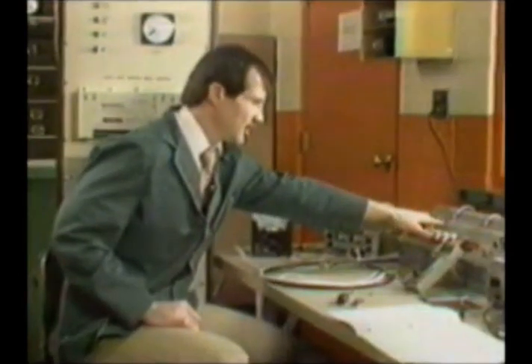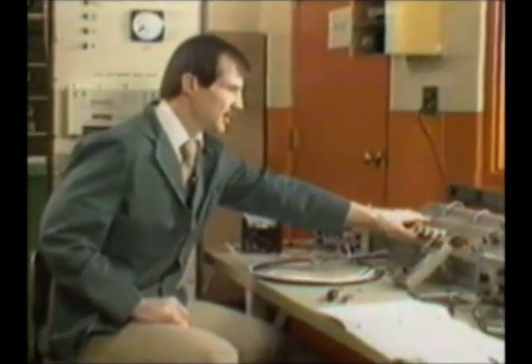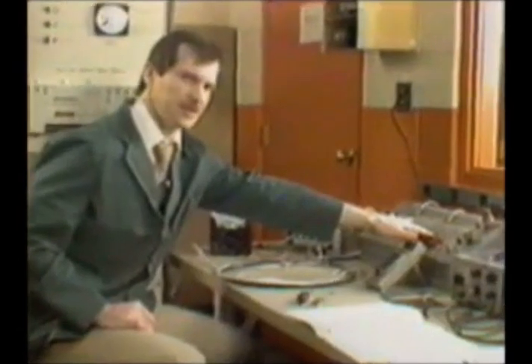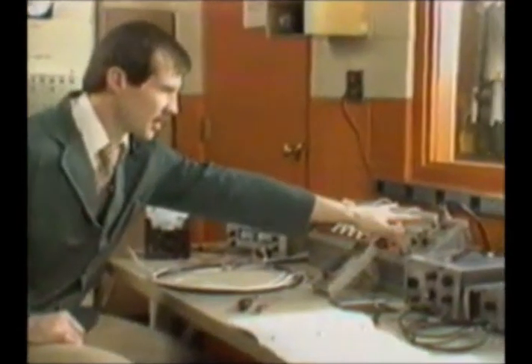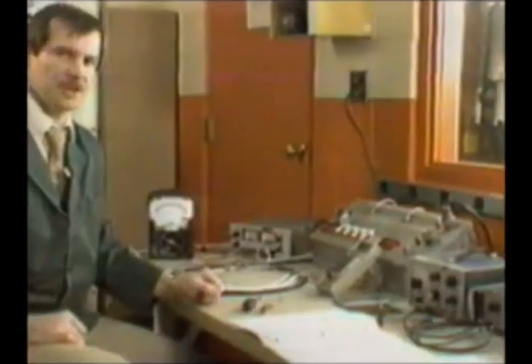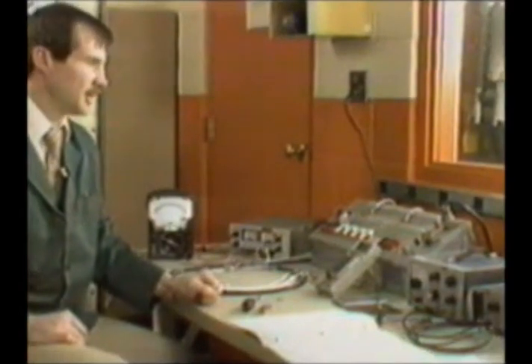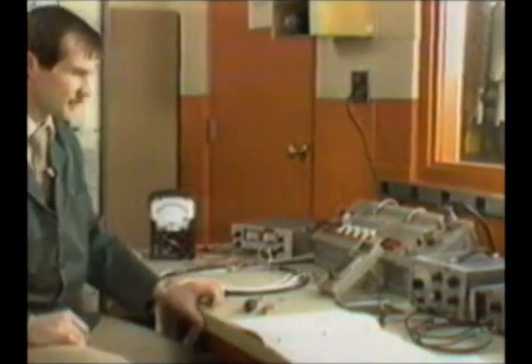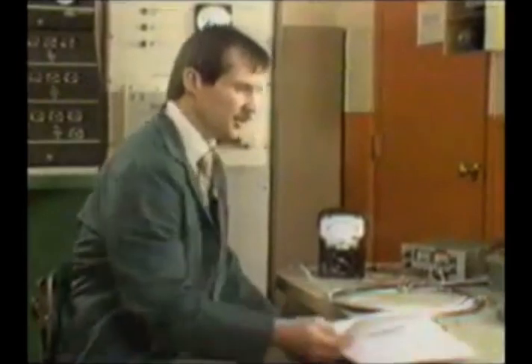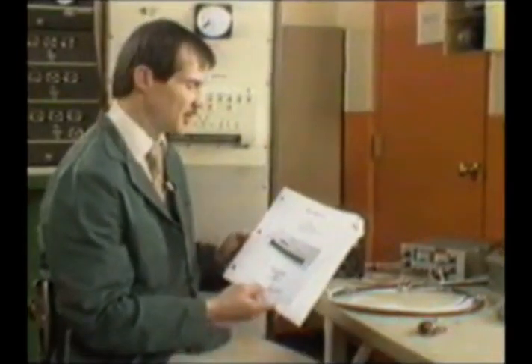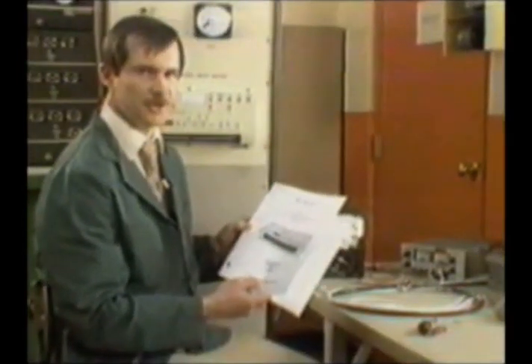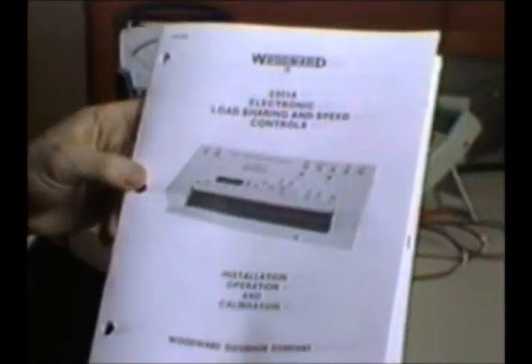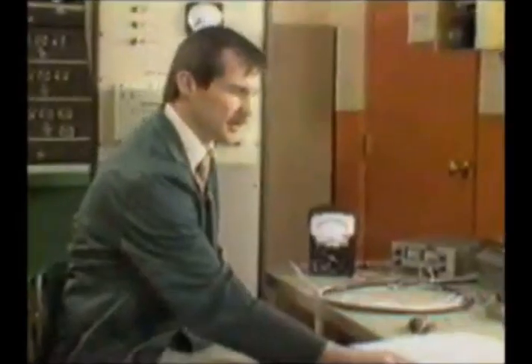With the wiring we can get our engine speed signal from the consolette here, and we can get our actuator signal from here. Over on the far right we have our potential and current transformer signal. These come from the generator and will be used for our load sharing section of the control. Today what I'm going to be mentioning to you mostly will come straight out of our 2301A electronic load sharing speed control manual. So if you have one of these manuals, make sure you read it before you get ready to install and adjust your 2301A.